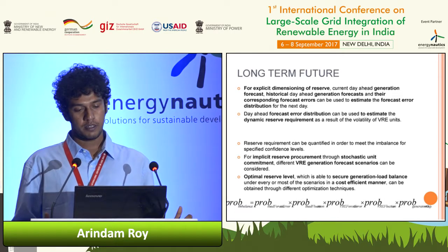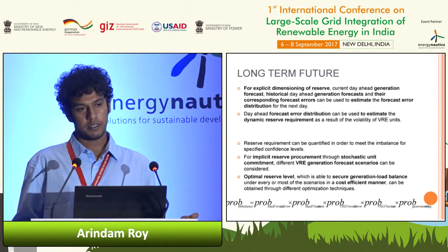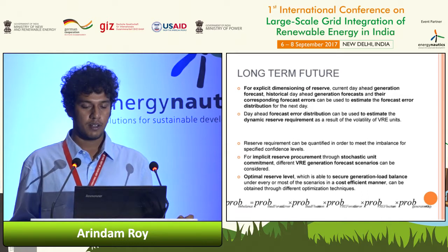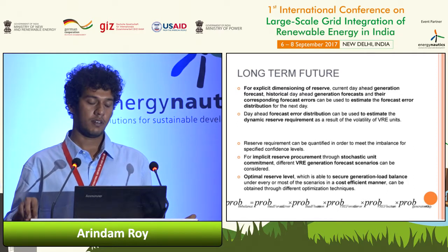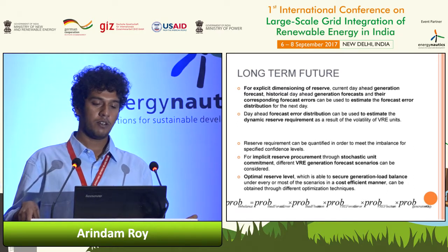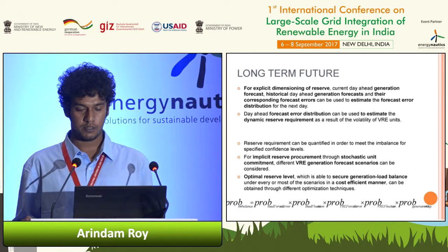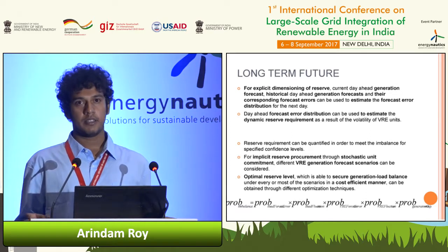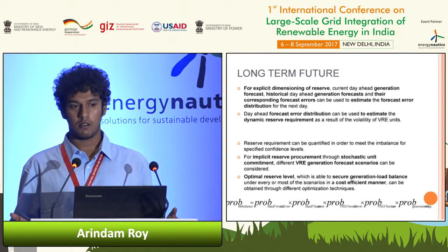The concentration and increased volatility of the VRE units may also result in an increase of the reserve requirement, particularly in the secondary and tertiary frame. And now this reserve can be taken into account either explicitly through setting reserve dimensioning, or it can also be implicitly included into the unit commitment process.